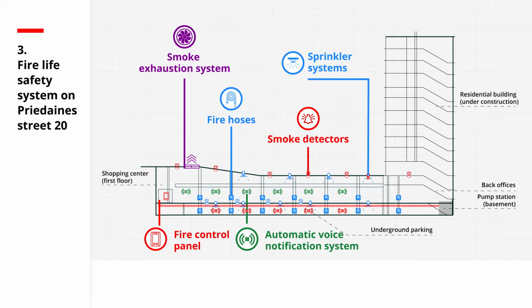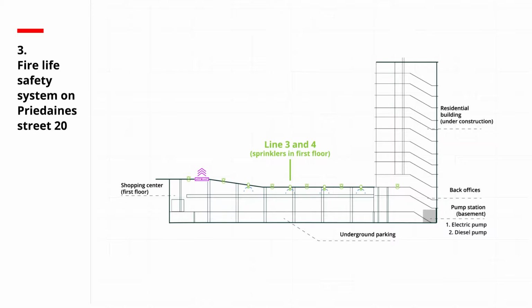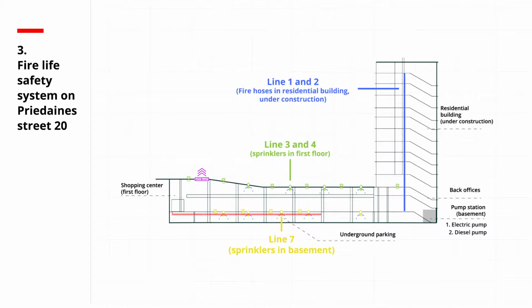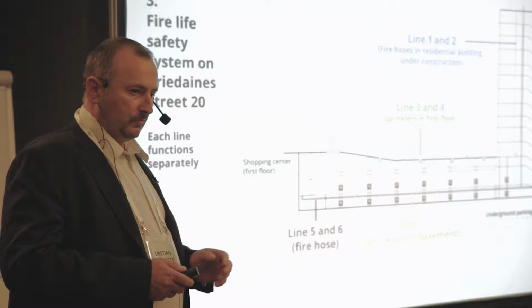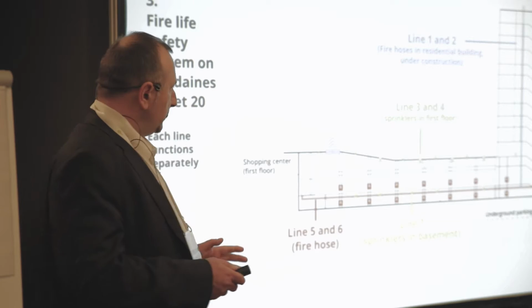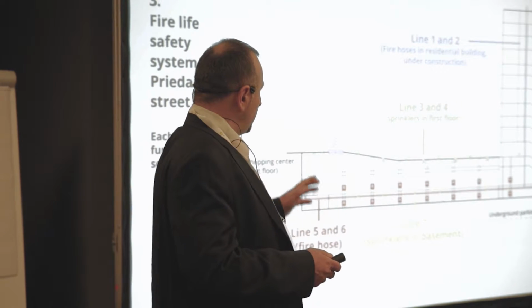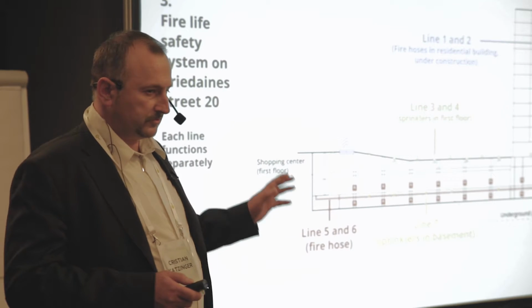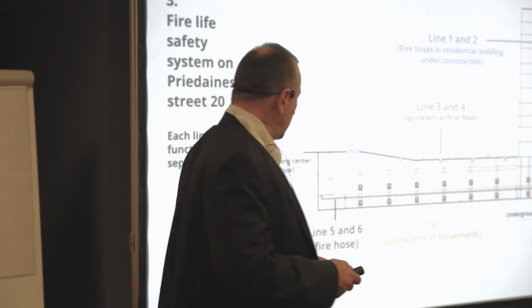That's how the firefighting system is designed in Priedaines Str 20. We've got here on the left side the pump station in the basement, from where the supplying of all systems came from. From there, we've got 7 lines that went off inside the building. Line 1 and 2 were for fire hoses in the residential building, which was still under construction at this time.